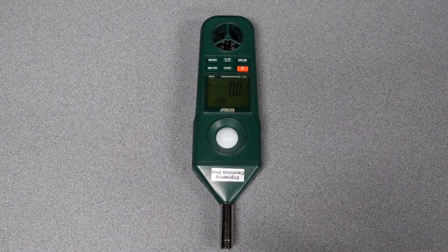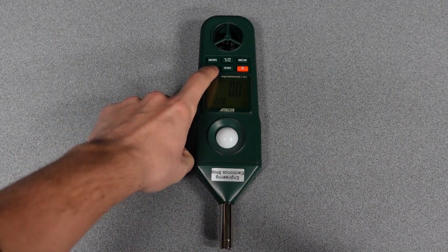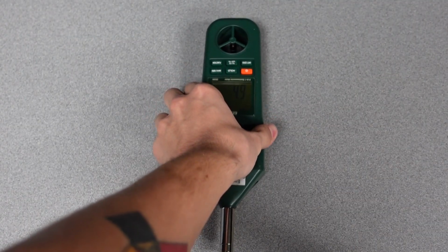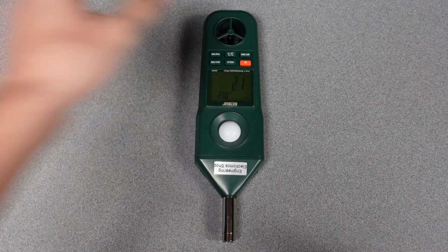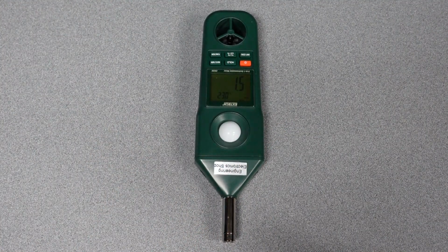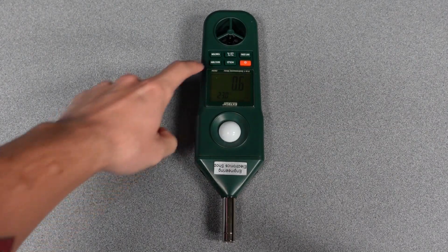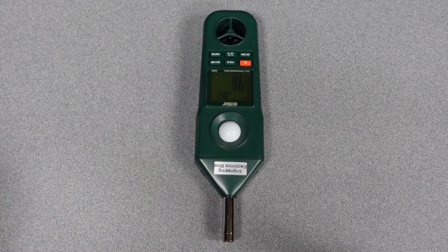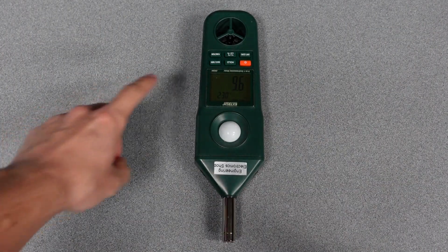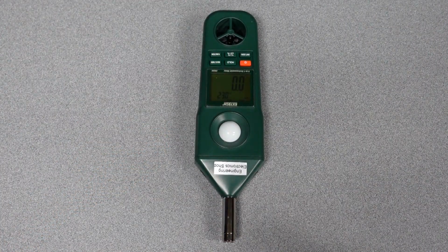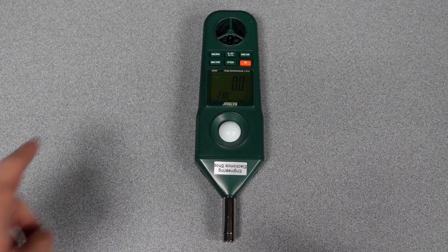With any function on this device, measurements can be recorded over an interval, after which the meter can show the maximum and the minimum readings over that interval. To do this, press the max/min button once to start recording. Then again to stop recording. It will first show the maximum, but pressing the button again will show the minimum. Holding the max/min button will clear the recorded interval.